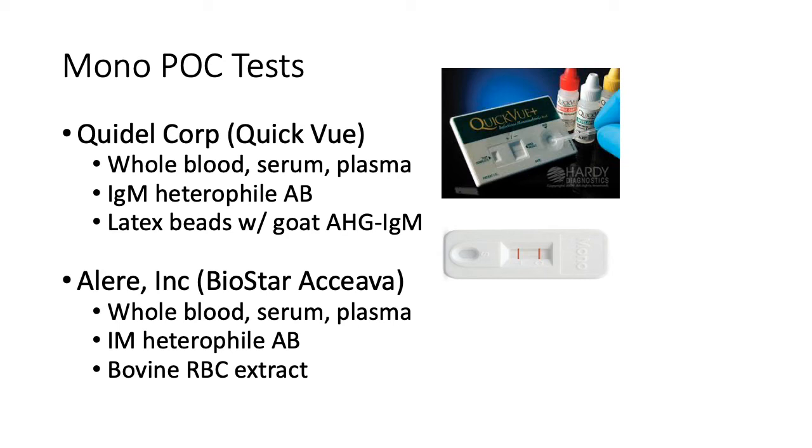If specific infectious mononucleosis heterophile antibodies are present in the sample, a sandwich of solid phase infectious mononucleosis antigen, antibody, and blue latex is formed. A vertical line will appear, resulting in a positive sign in the read result window. If the antibody is not detected, the read result window will only contain the pre-printed blue horizontal line, indicating a negative result.